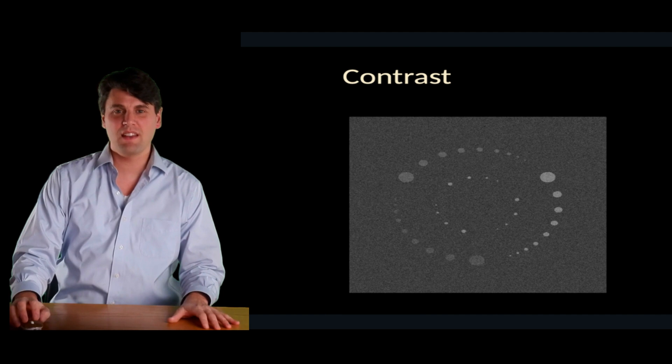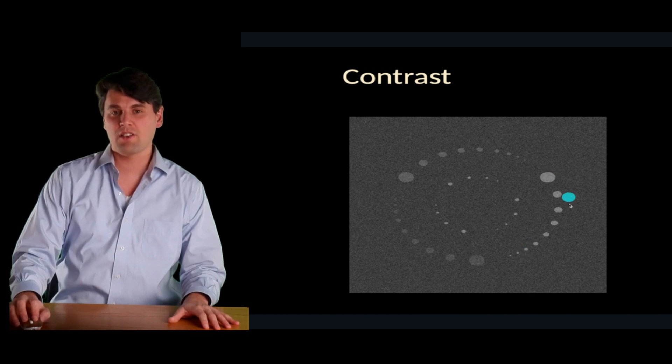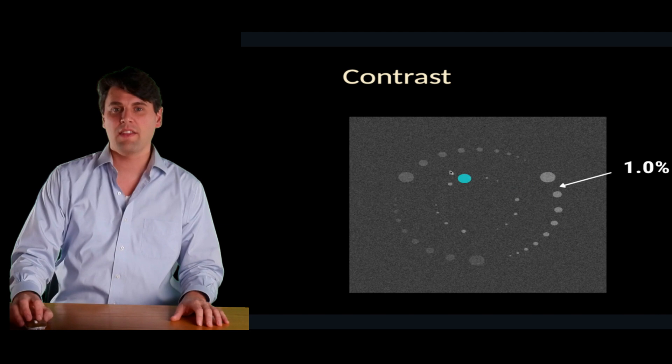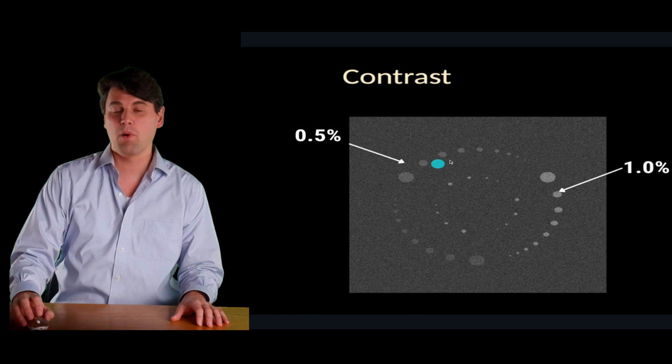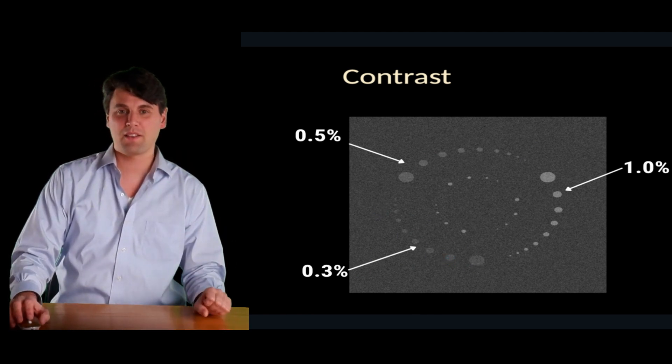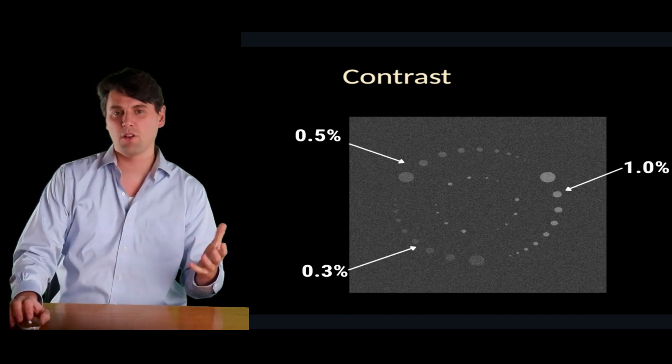This is a phantom we often use in CT imaging, where you can see different lesions and how well they stand out from the background. These lesions here are actually 1% different in their attenuation values for our CT image, and we call that 10 Hounsfield units. And then these up here are actually 5 Hounsfield units or 0.5%. And over here, we're talking about 0.3% or 3 Hounsfield units in comparison for those lesions with respect to the background. The question is, if you had a relatively small lesion which is relatively low contrast, would you be able to differentiate that in your CT image?